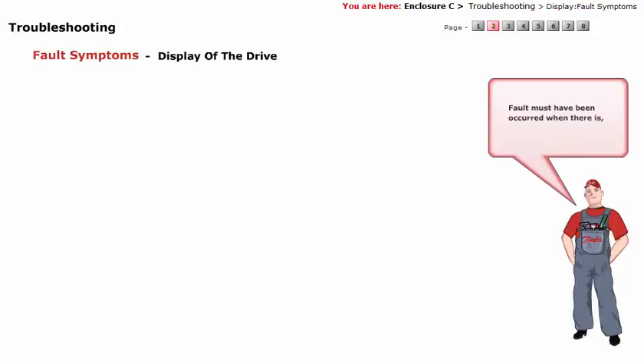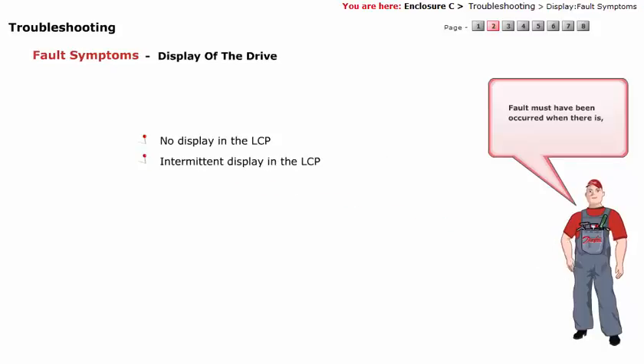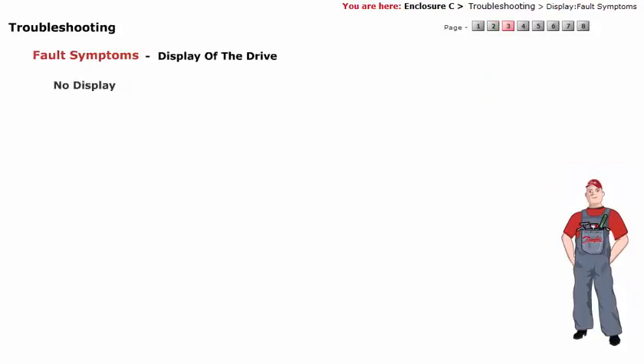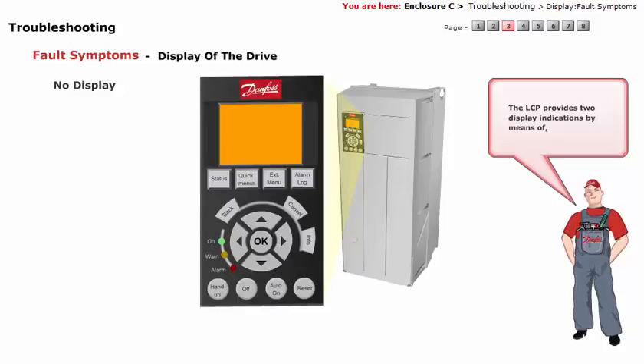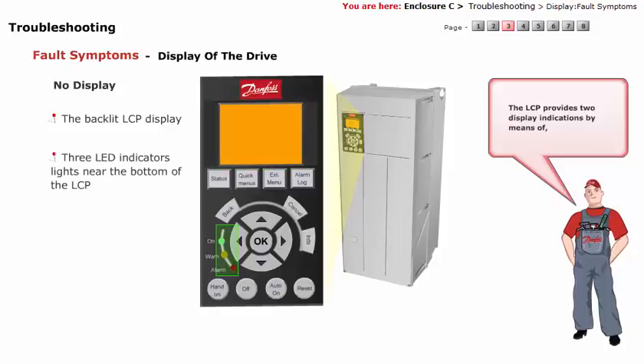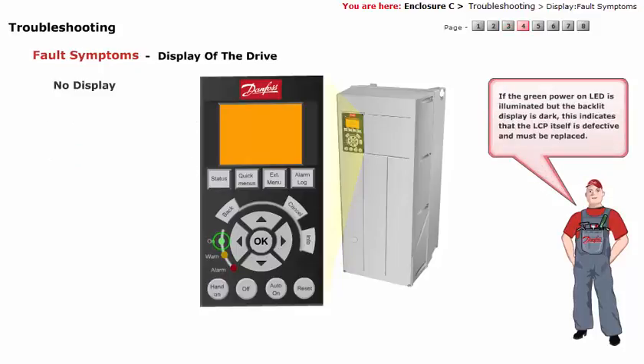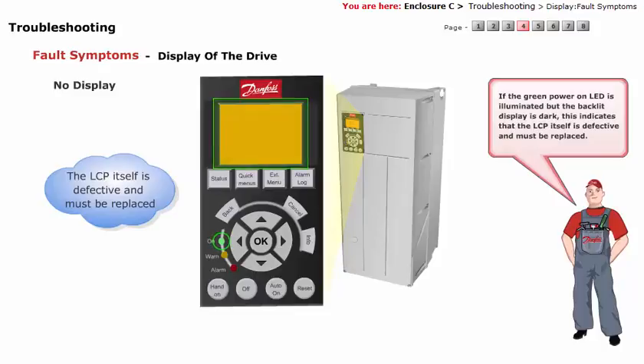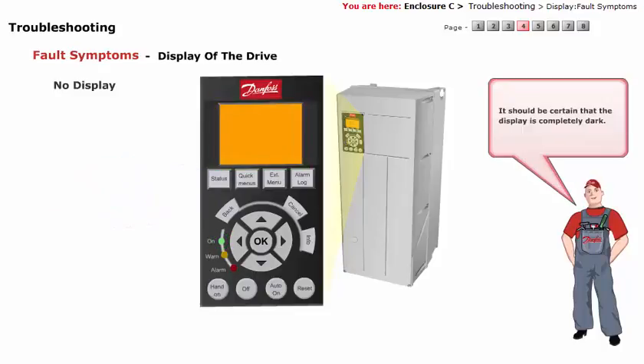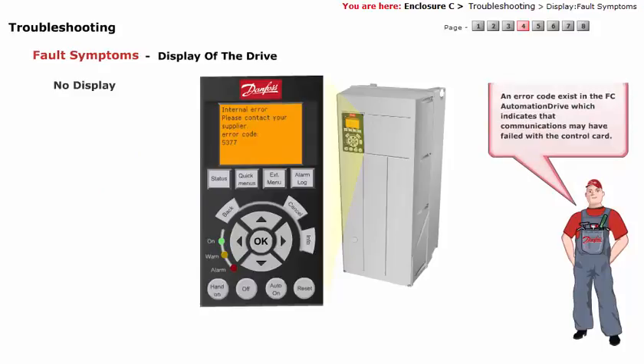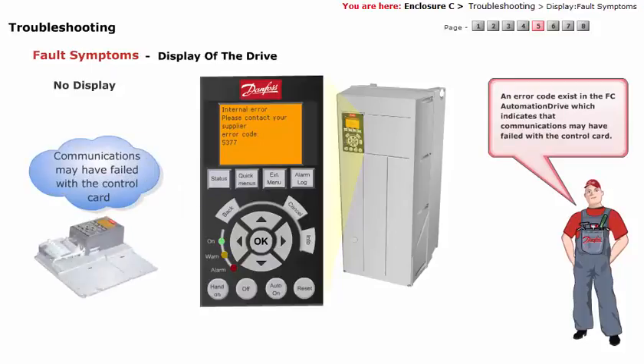A fault may have occurred when there is no display in the LCP, or there is an intermittent display in the LCP. The LCP provides two display indications by means of the backlit LCP display and three LED indicator lights near the bottom of the LCP. If the green power-on LED is illuminated but the backlit display is dark, this indicates that the LCP itself is defective and must be replaced. It should be certain that the display is completely dark.